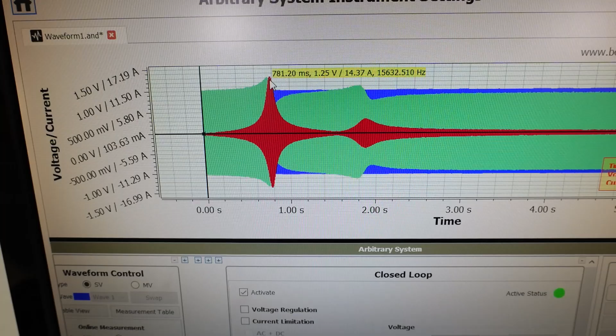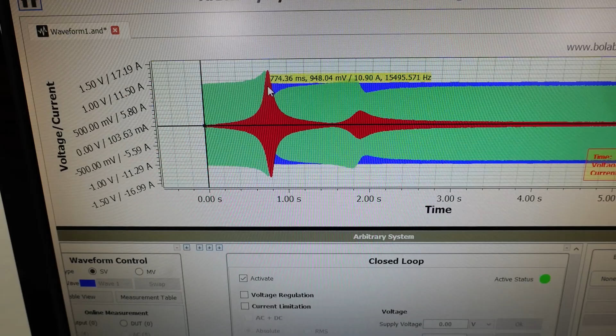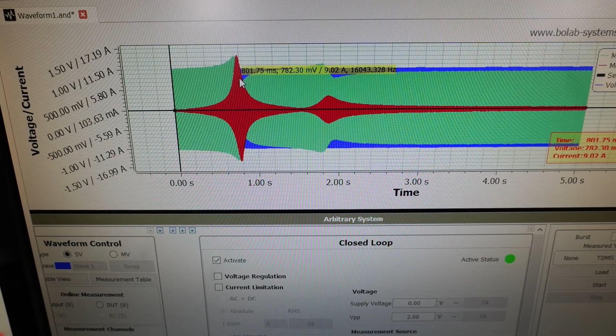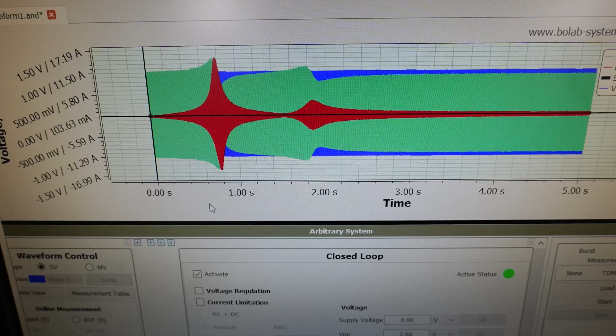As we see here, red is our current. Exactly at 16 kilohertz, as determined in the impedance graph, we see our resonance. We said there is the lowest impedance, so the current is at its maximum. We also found in our impedance graph another resonance range, in this case at approximately 37 kilohertz. Out of that, the current is going to undefined values, and the standards say this current must be limited.